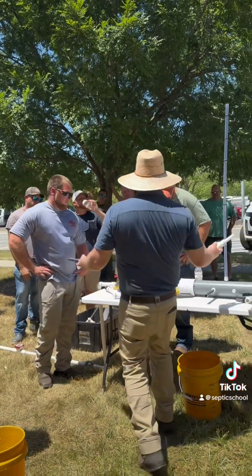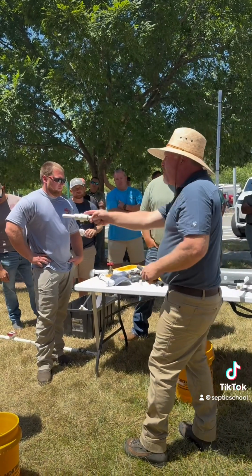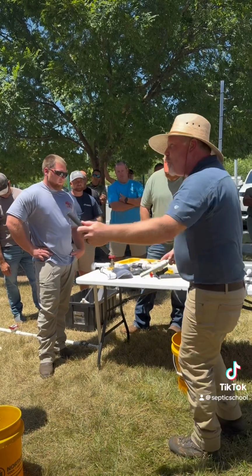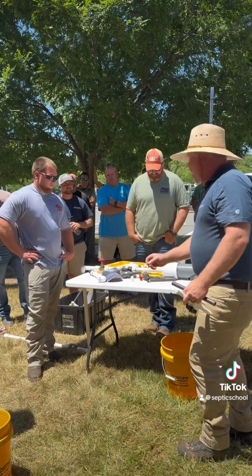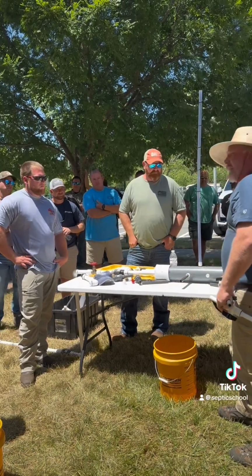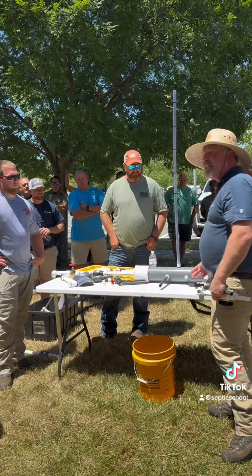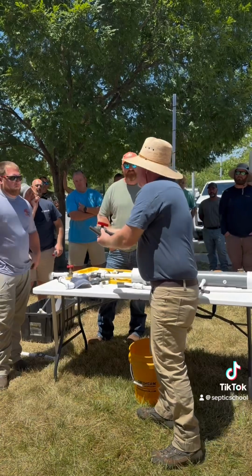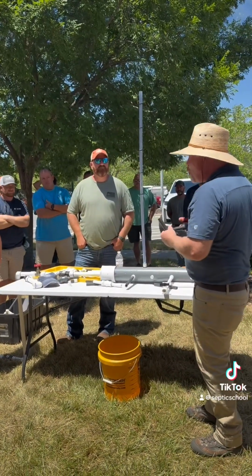So all of this today, the whole stuff here is to show you this. Little things that you guys do on installation have big impacts on the precision here. To do this right, everything is consistent. They're all the same length. The tap placement is all the same on these, meaning the valve placement. So don't put your valve at the end, don't put it here, put them all roughly in the middle and be consistent. The valve selection, if I'm going to use these valves, I'm using those valves throughout, right? And if we do the same, these things can be incredibly precise.